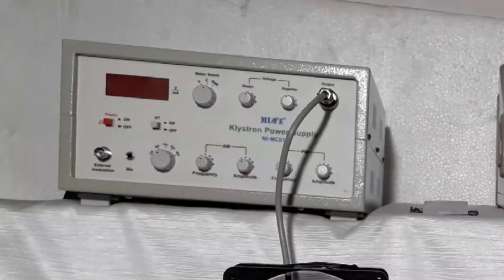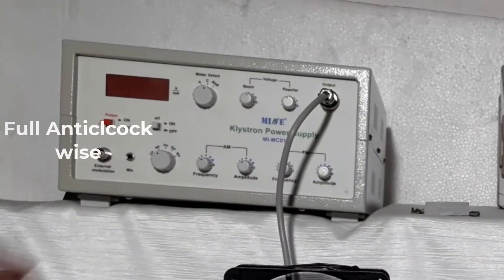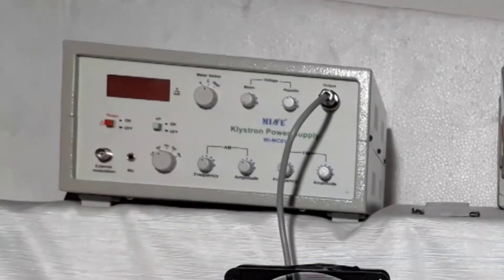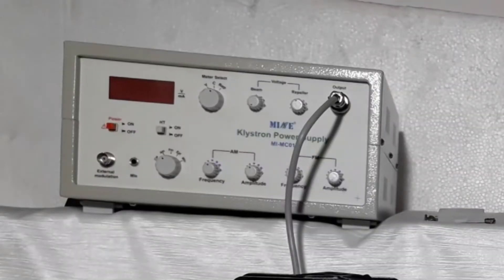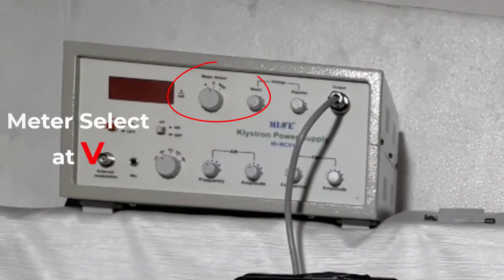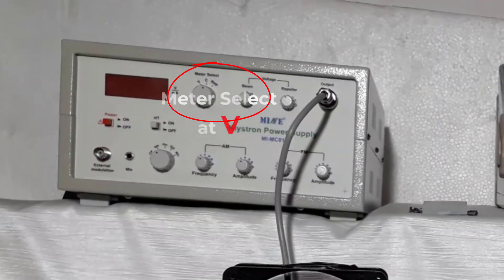Set beam voltage knob at fully anti-clockwise. Set repeller voltage knob at fully clockwise position. Set meter select knob at V, that means beam voltage.